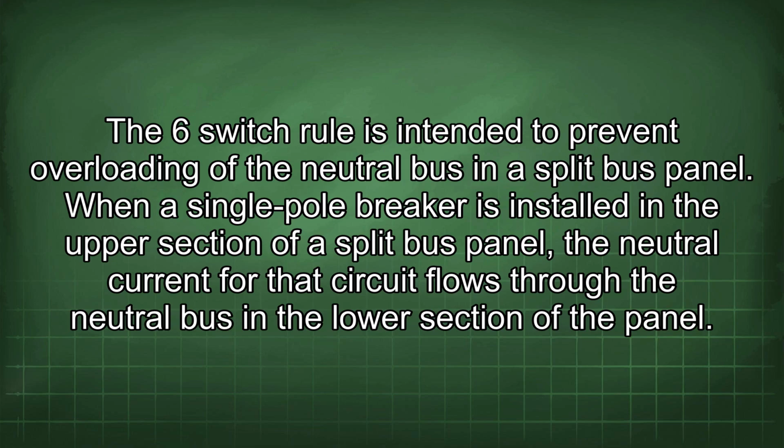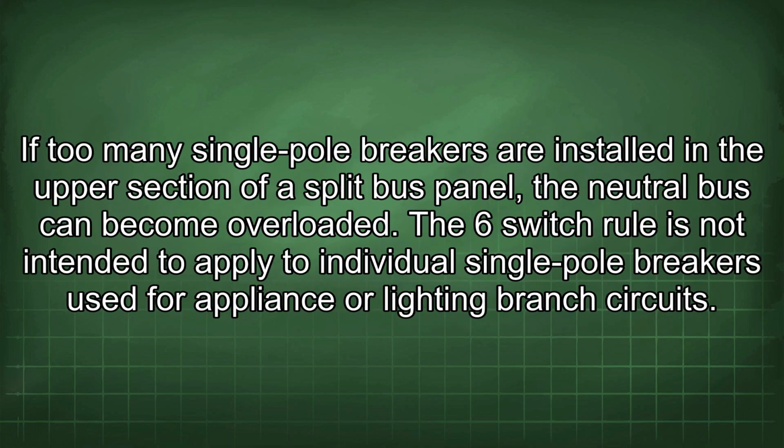panel. When a single-pole breaker is installed in the upper section of a split bus panel, the neutral current for that circuit flows through the neutral bus in the lower section of the panel. If too many single-pole breakers are installed in the upper section of a split bus panel, the neutral bus can become overloaded.